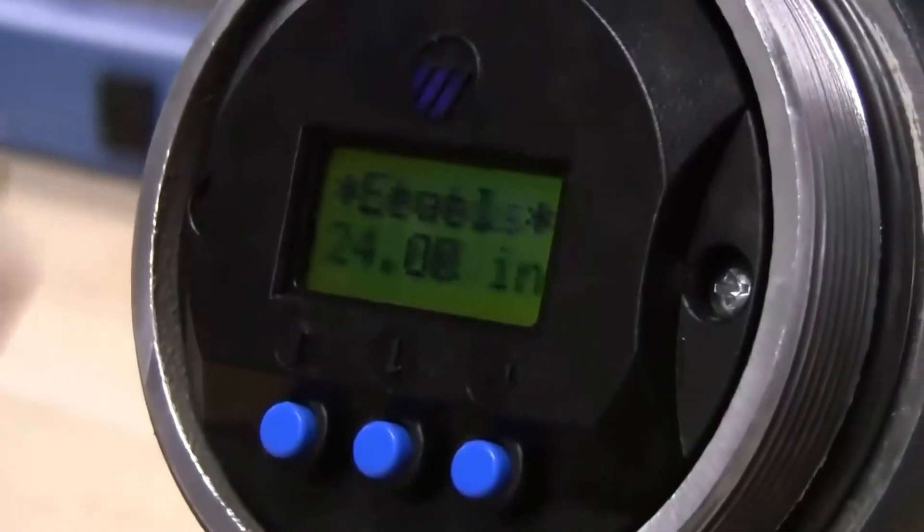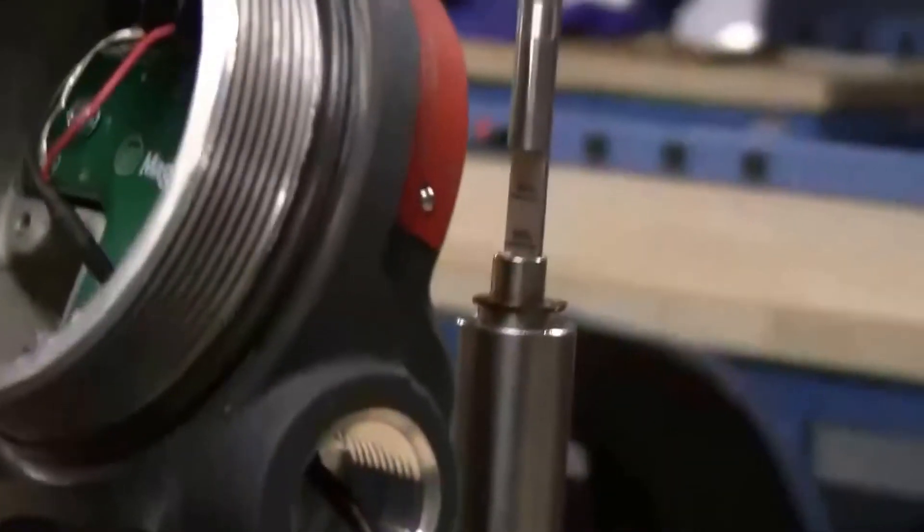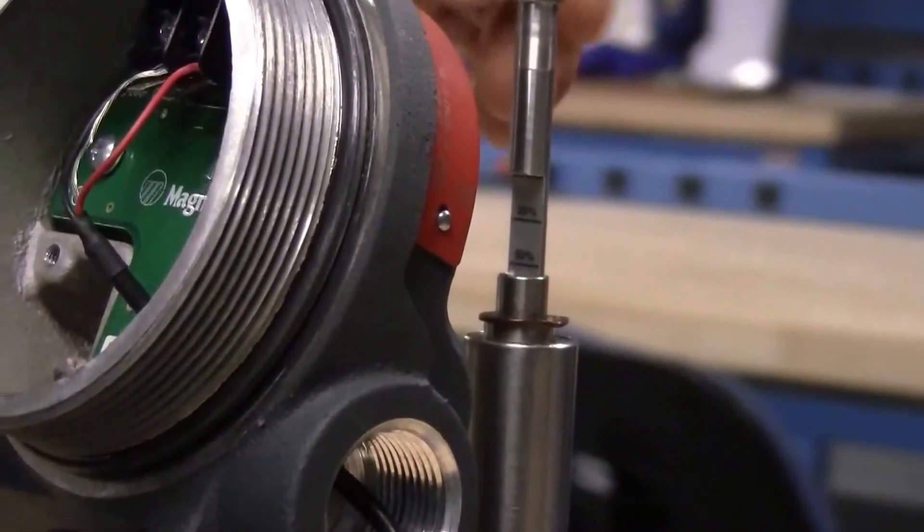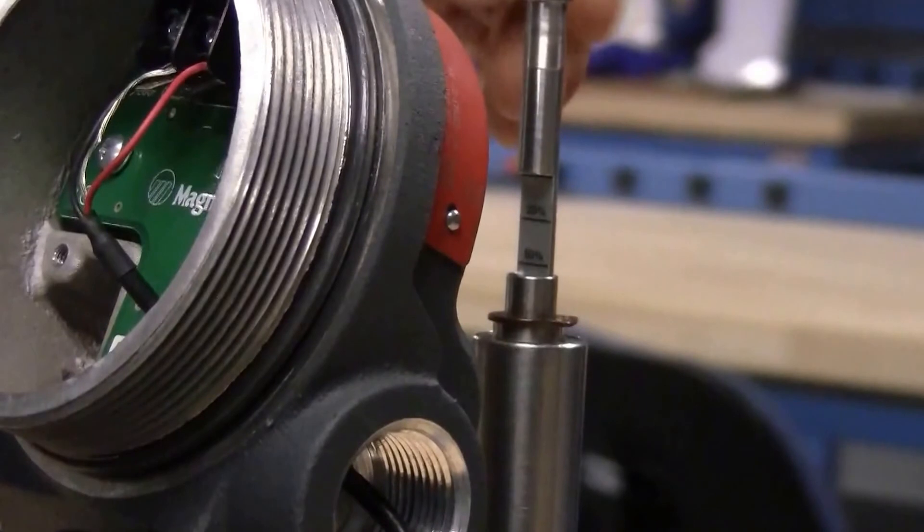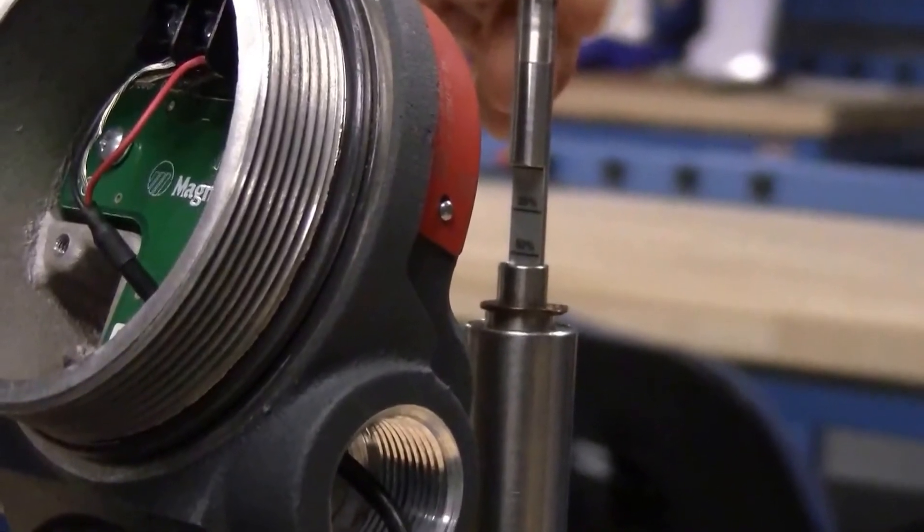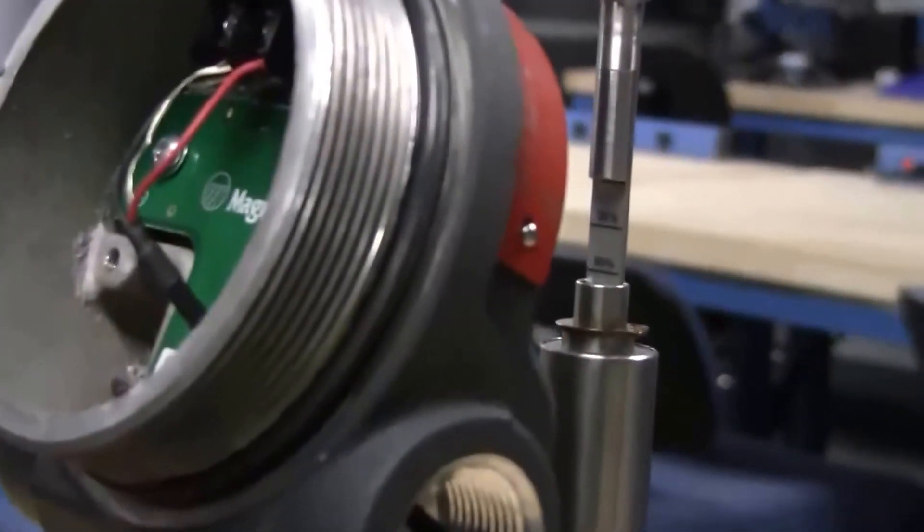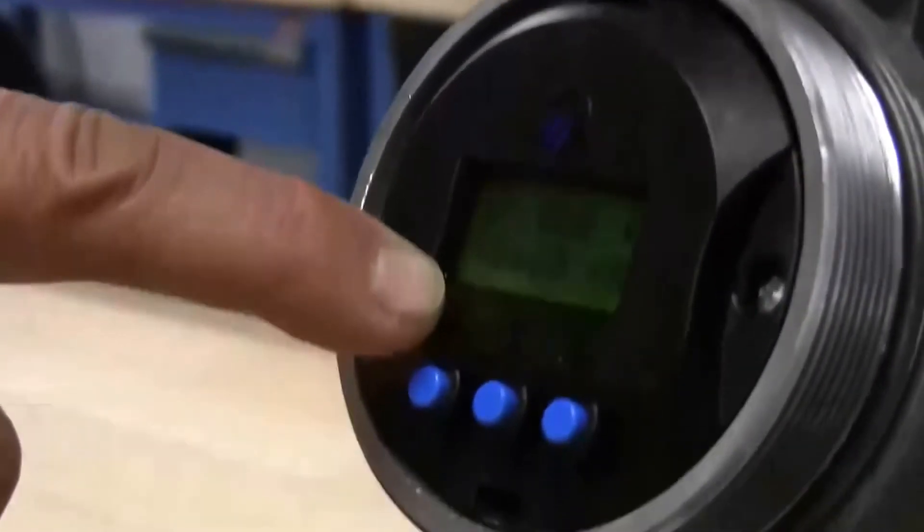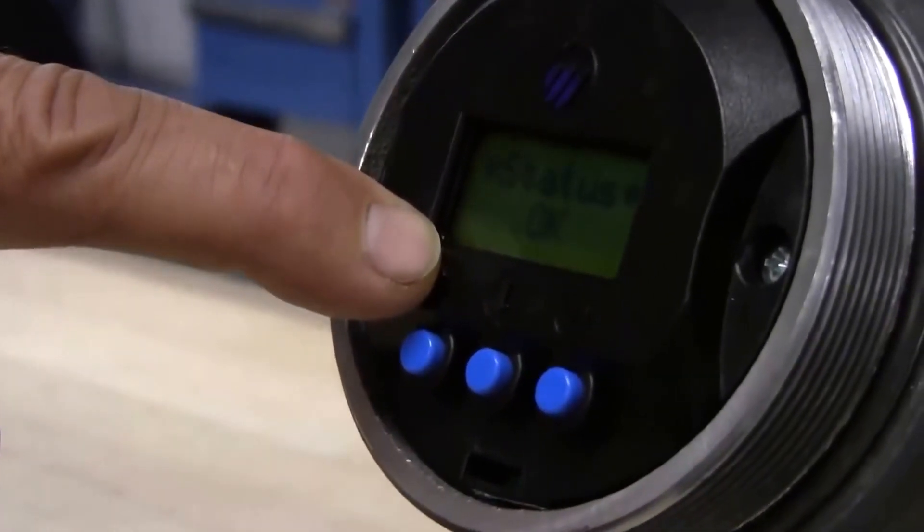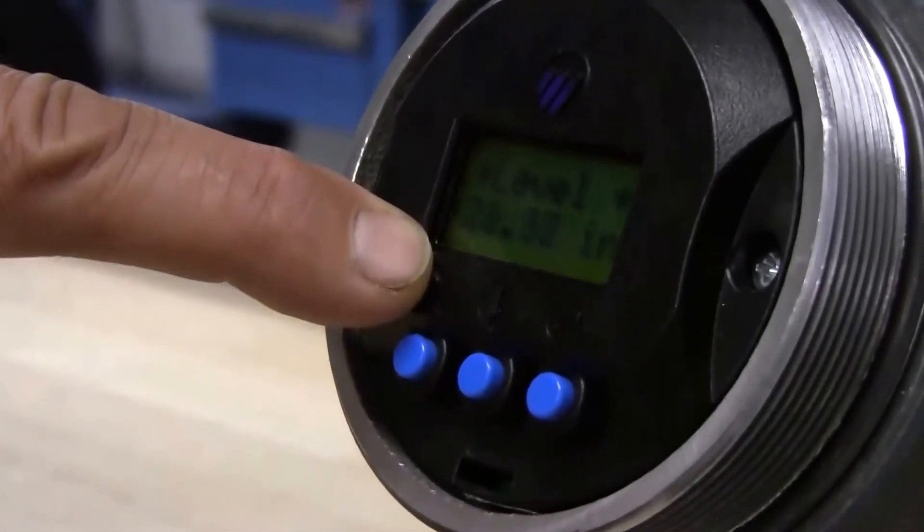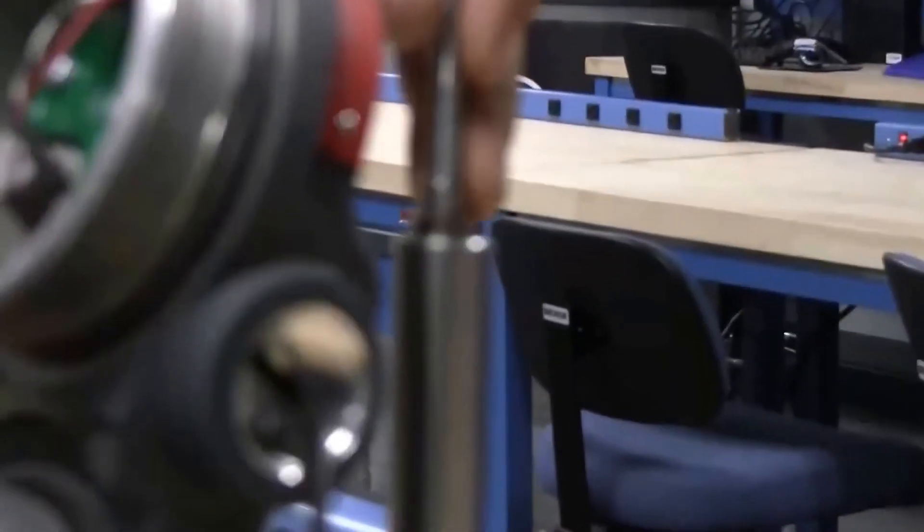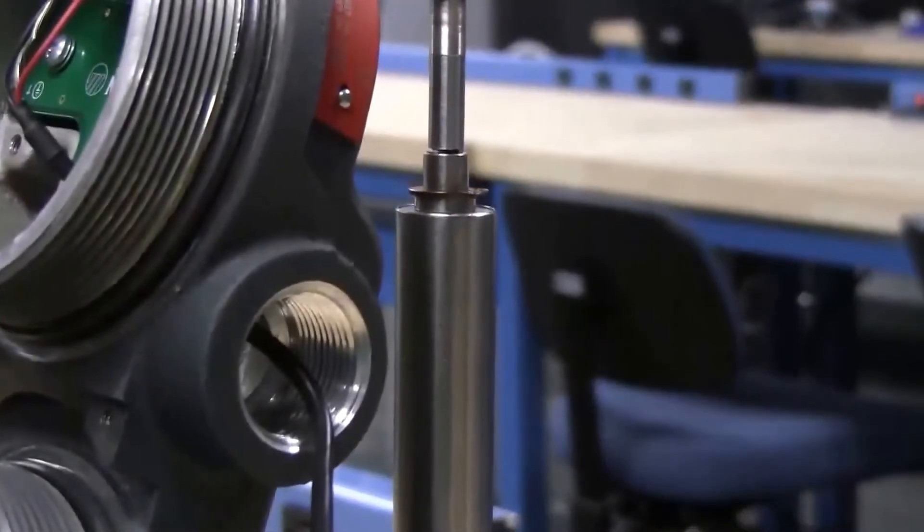And you can then down arrow back to your run mode. And there's our run mode. So now, if we can turn this a little bit, you can see the LVDT core. Right now, the LVDT is at 50 percent, and you can see we're just about at 24 inches, 50 percent, and 12 milliamps. I'll go ahead and change it to basically a zero reading on the displacer. So we'll push that LVDT core down to simulate zero inches on the displacer, and you can see we're showing basically an output of zero and very close to four milliamps there.